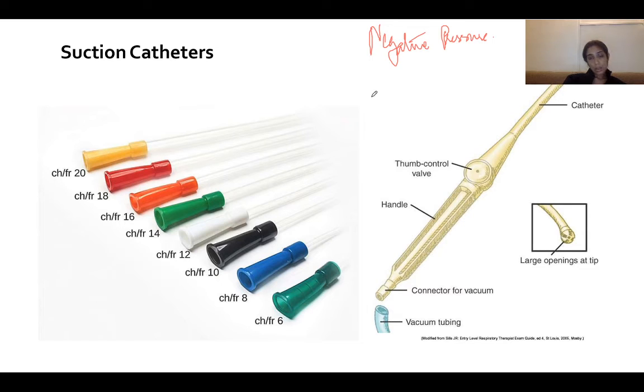So now the equipment consists of vacuum sources. The suction apparatus requires a source that can generate a subatmospheric pressure. The most common source of vacuum is the pipeline system, which is attached to the wall of the operation theatre. Then there are also portable suction units. Portable suction units are basically to be used in locations where piped vacuum is not available. So piped vacuum gets connected to a suction apparatus and exerts its pressure, right?